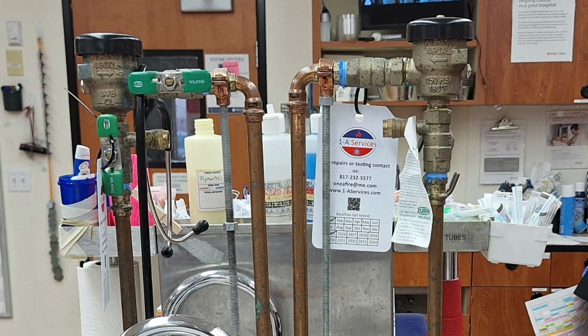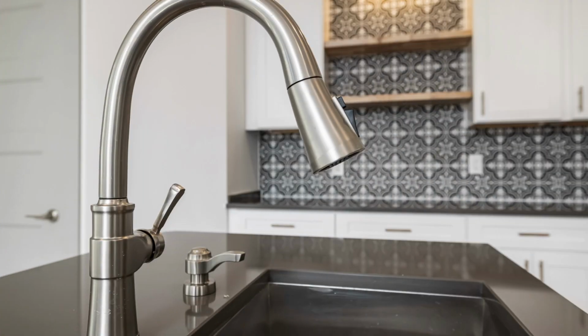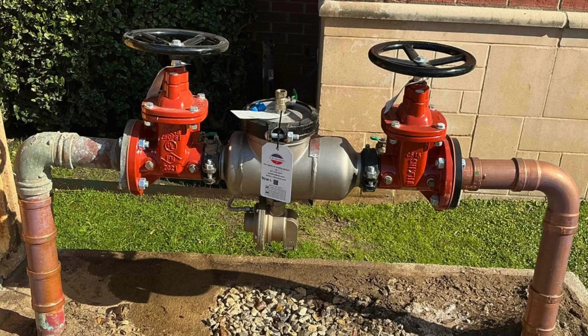So how do we keep our water safe? Backflow prevention devices like vacuum breakers, air gaps, and reduced pressure zone assemblies are key. These devices stop water from flowing in the wrong direction, effectively preventing contamination altogether. But simply having them isn't enough - they need to be inspected and tested regularly. A backflow test is done to ensure your backflow device is working correctly, and it's often required by local authorities or water districts. If your device fails, it either needs to be repaired or replaced to keep your water supply protected.